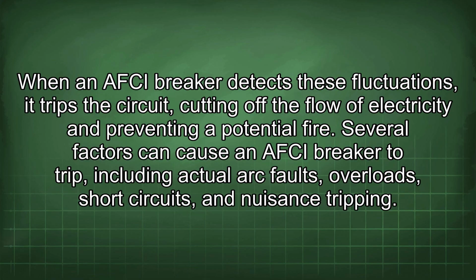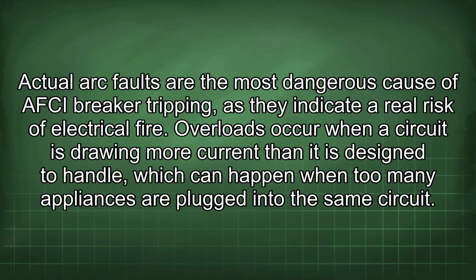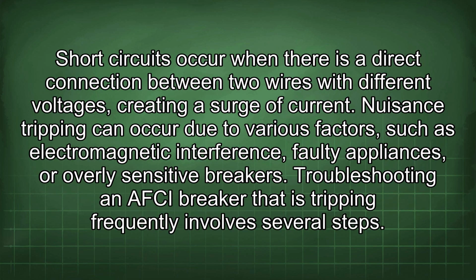Several factors can cause an AFCI breaker to trip, including actual arc faults, overloads, short circuits, and nuisance tripping. Actual arc faults are the most dangerous cause of AFCI breaker tripping, as they indicate a real risk of electrical fire. Overloads occur when a circuit is drawing more current than it is designed to handle, which can happen when too many appliances are plugged into the same circuit. Short circuits occur when there is a direct connection between two wires with different voltages, creating a surge of current. Nuisance tripping can occur due to various factors, such as electromagnetic interference, faulty appliances, or overly sensitive breakers.